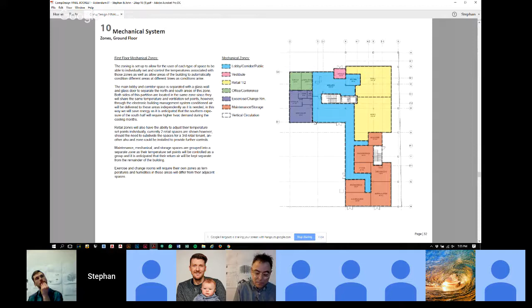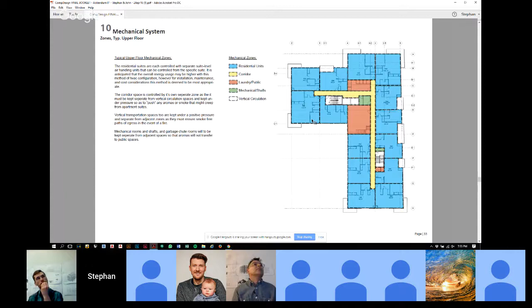So it could have a solar heat gain coefficient, so we'd want to condition them separately. This is your typical upper story floor. Corridors again are their own zone because they're conditioned and pressurized, and the suites again are their own.